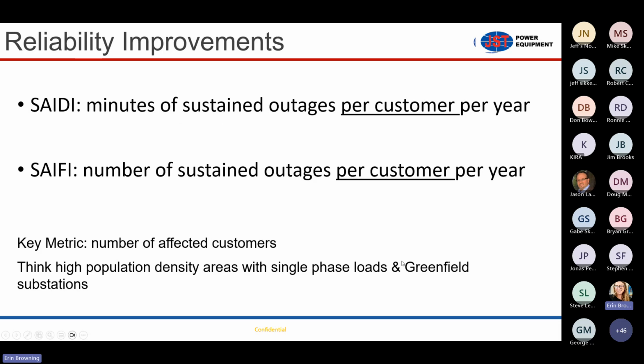What I would say is that when you're talking to customers about greenfield substations, especially substations serving high population density areas, or substations dedicated to new housing developments, those are going to have a lot of single phase loads, where customers might be more inclined to perform single phase trip, single phase lockout, or even single phase trip, three-phase lockout all the way back to the substation. It's where there are single phase loads that they're going to want to do that. They're not going to want to do this on three-phase loads. In commercial and heavy industrial, where you have a lot of three-phase loads, you're not going to be doing single phase trip, single phase close.